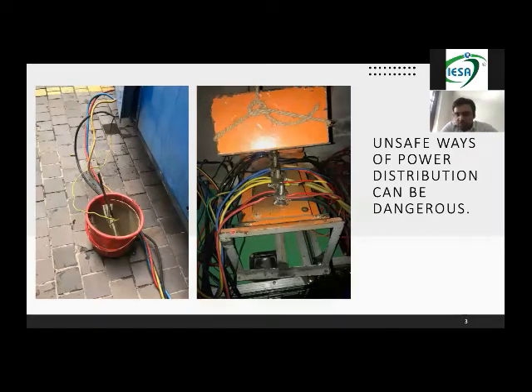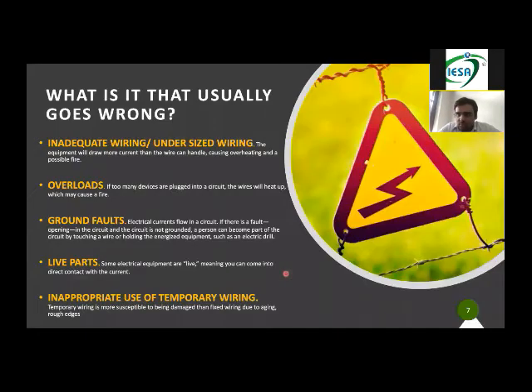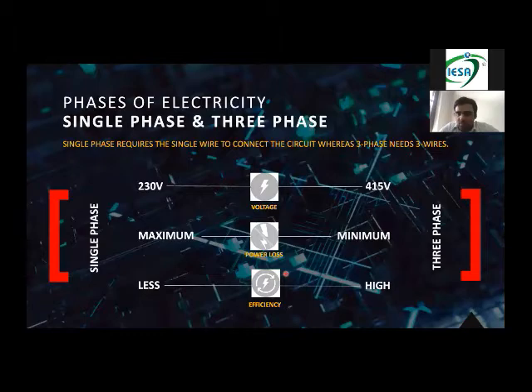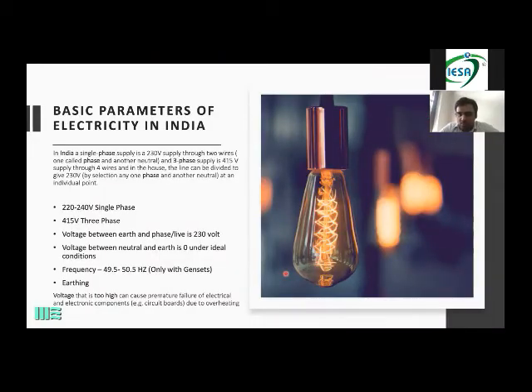Normally, this metal box needs to be earthed properly. Normally there has to be a bolt over here and a green color wire has to be connected to it. If you put the multimeter on this and this, you will always get 220 to 240 volts. And if you check neutral to your earthing, you will always get 0 volts under ideal conditions. That can go up to 0 to 5 volts also. If it is 0 to 5 volts, your electricity is good to go. There is no problem. Only then you need to start the electricity. Otherwise, anything can go wrong on site.